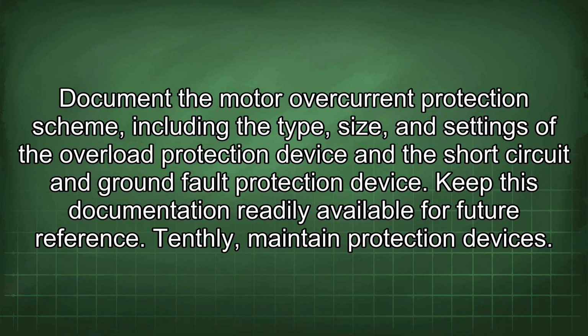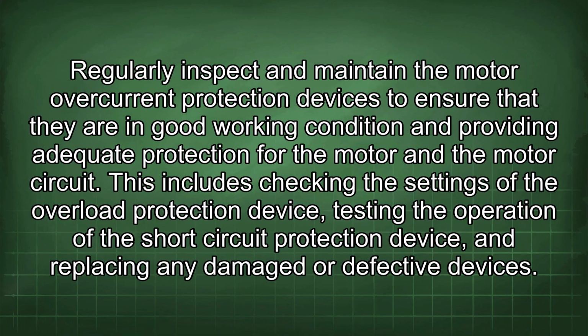Tenthly, maintain protection devices. Regularly inspect and maintain the motor overcurrent protection devices to ensure that they are in good working condition and providing adequate protection for the motor and the motor circuit. This includes checking the settings of the overload protection device, testing the operation of the short circuit protection device, and replacing any damaged or defective devices.